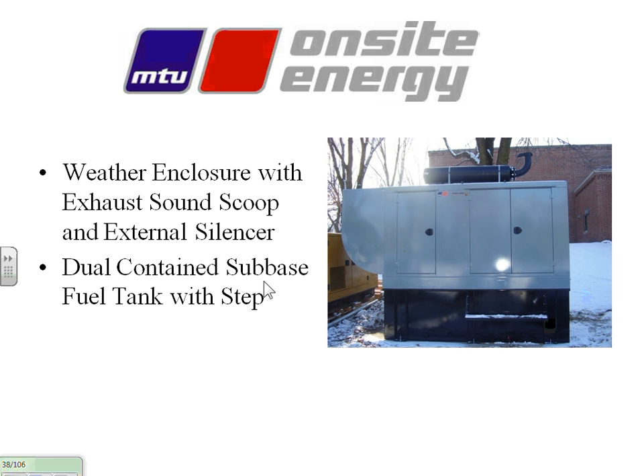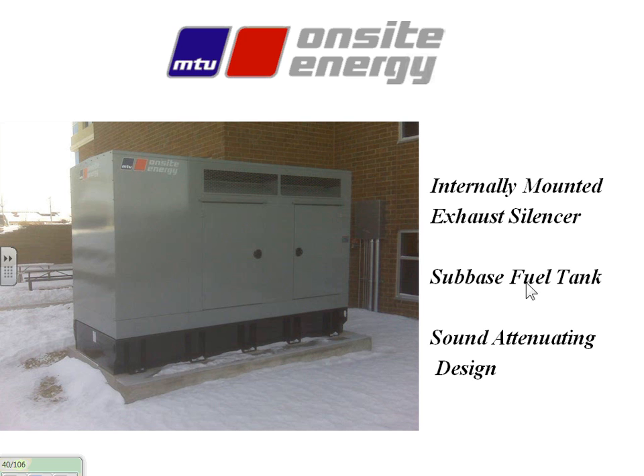Down here, this black part, that's a dual containment fuel tank. This is a diesel set, obviously. And that's the tank within a tank sitting right underneath the generator set. This little piece there is a step, because the NFPA and the NEC say we have to be able to get to the control. So we put a step on the tank to make sure that you're able to reach that. Just a little additional part of the design.